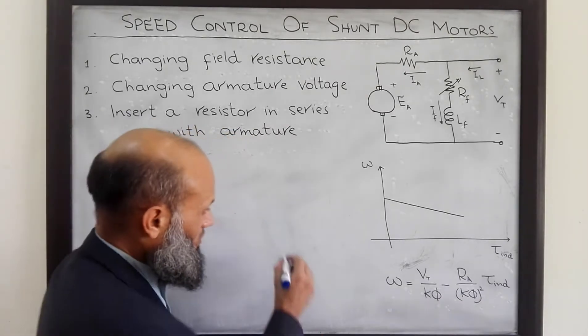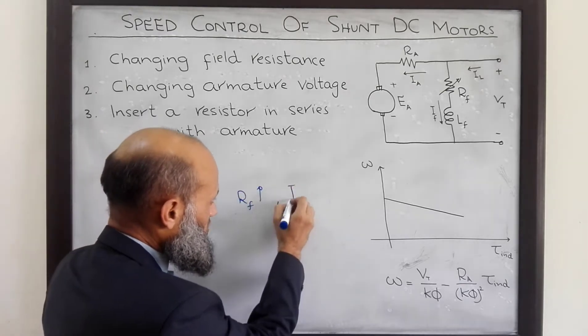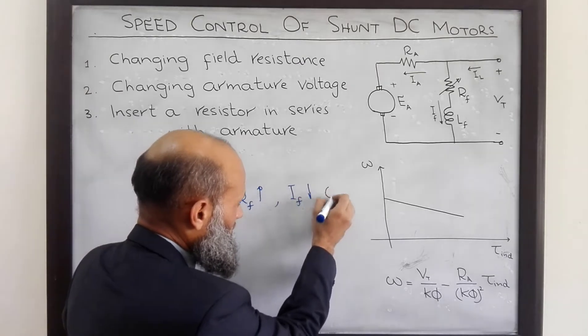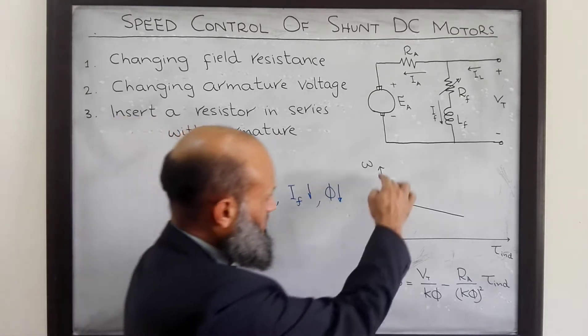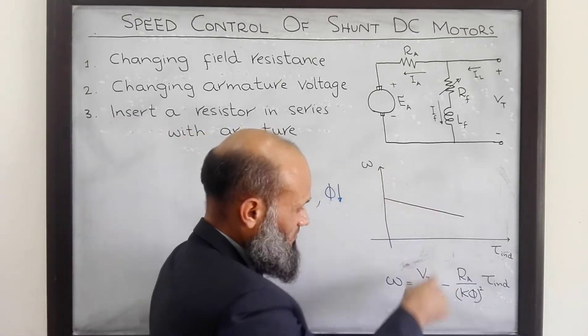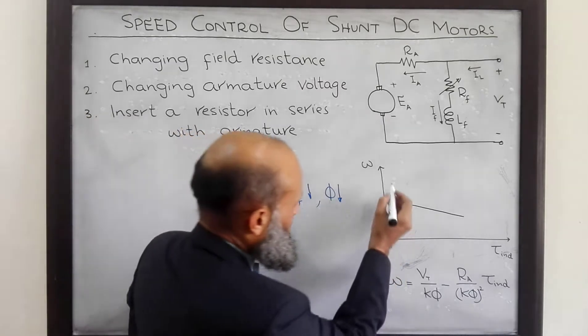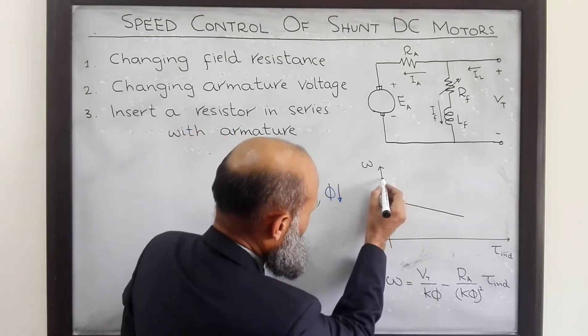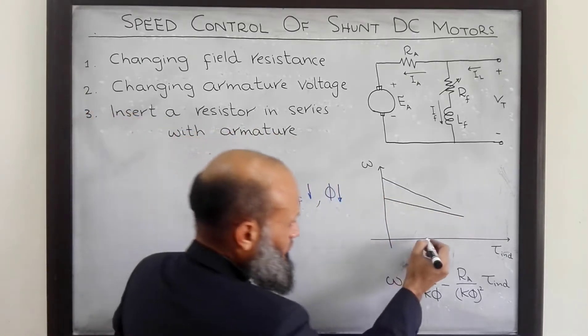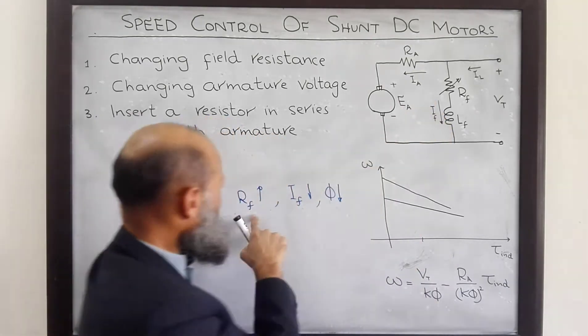If we increase field resistance, that results in a decrease in current, which in turn results in a decrease in flux. A decrease in flux is associated with an increase in the vertical intercept of this line and also a steeper slope. That is, by decreasing flux we get these torque-speed characteristics. So for a given load, if we increase the field resistance, flux decreases and the machine runs at a higher speed.